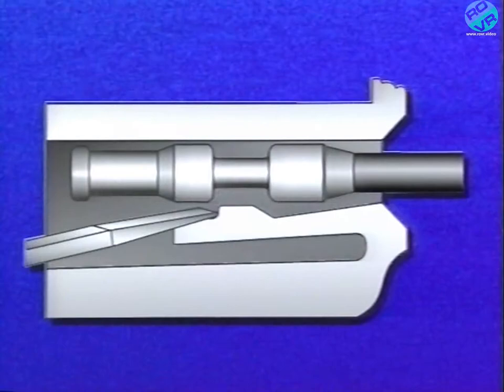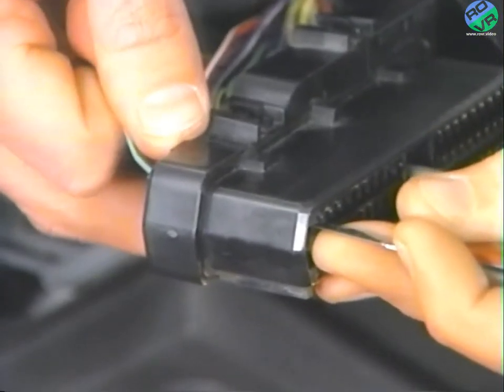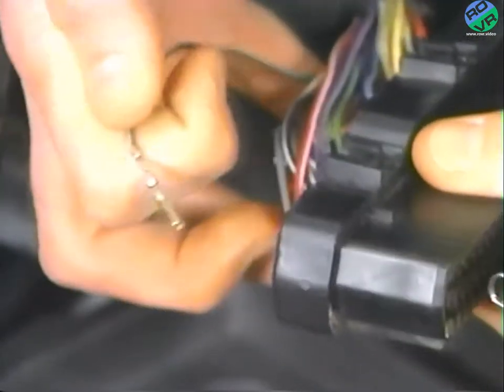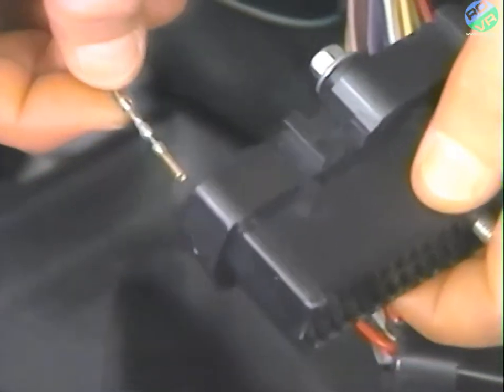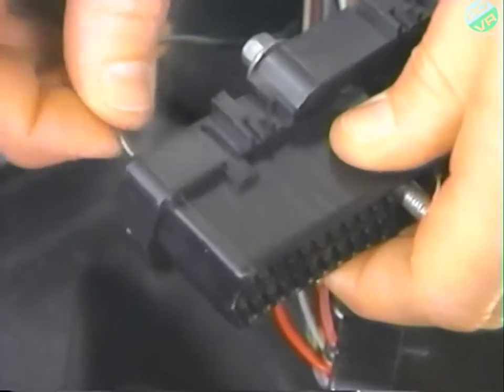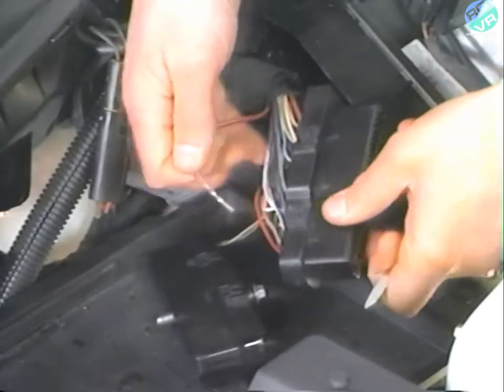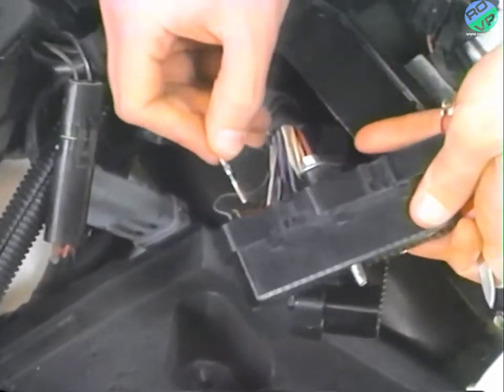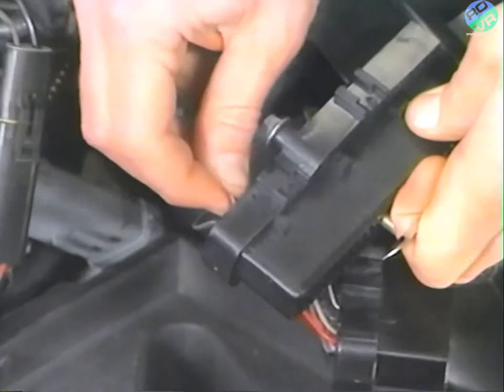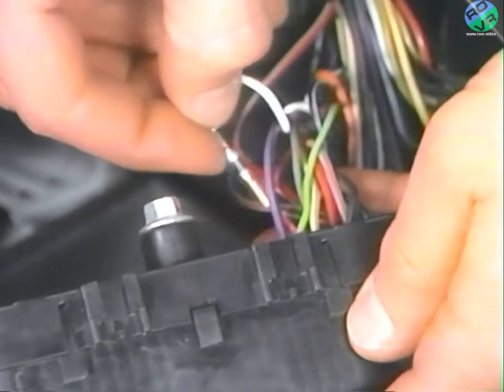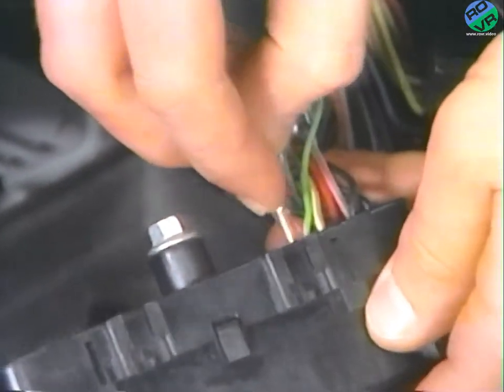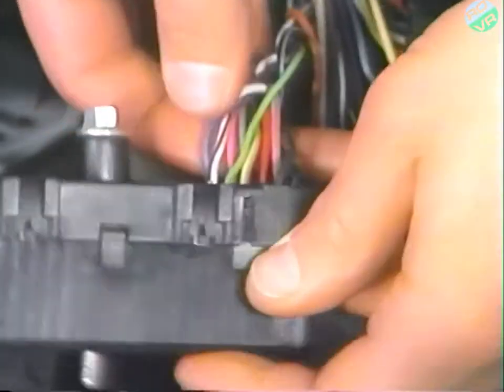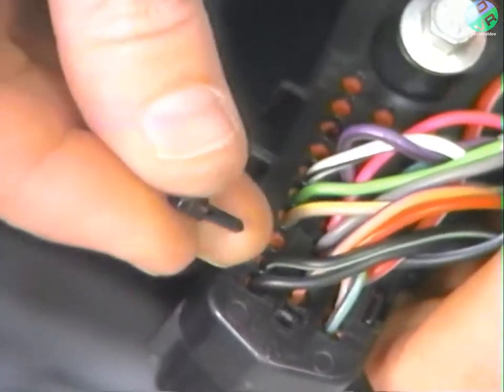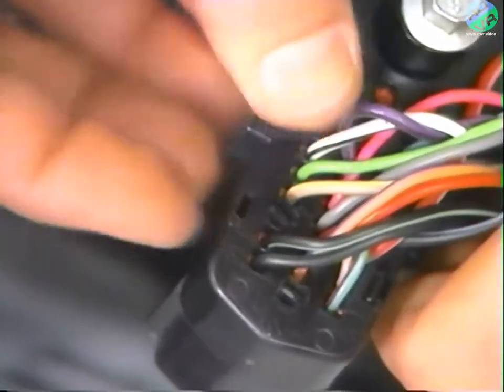A small locking finger keeps each terminal locked in place inside the insulator. To remove a wire, move the locking finger away from the terminal with a small knife while pulling on the wire. Insert the separated wire in the same cavity of the new insulator, making sure that the terminal locks inside the insulator. To avoid mixing up the wires, it's best to remove and replace one wire at a time. Continue to remove and install each wire, making sure that it's inserted into the proper cavity. When inserting bus wires, make sure that they are twisted up to the insulator and that there are no other wires between them. A 60-way connector replacement package also includes cavity plugs for connector cavities without wires.